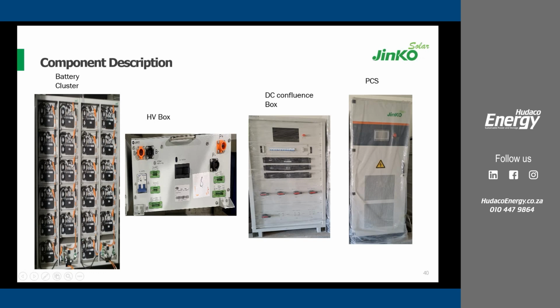Then we have all the terminations. The series connection is terminated on the high voltage box, which basically has the DC breaker, and also the second level of the BMS. Each of the batteries will also have a battery management unit, the BMU.